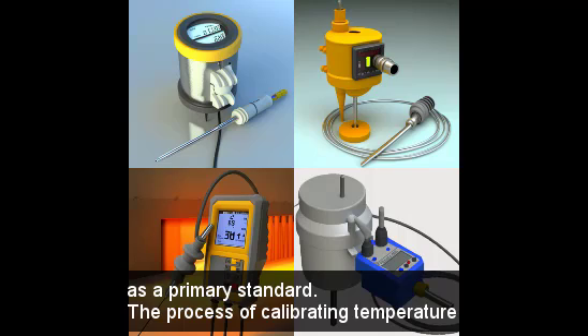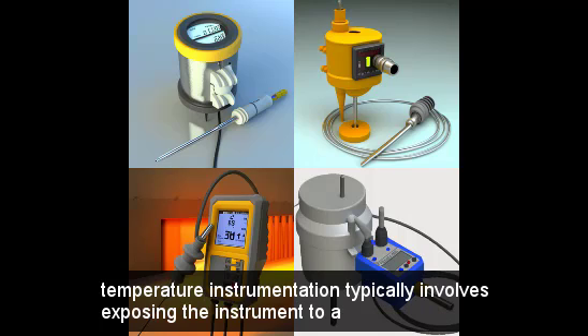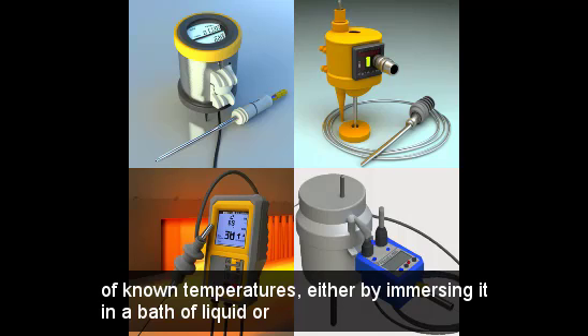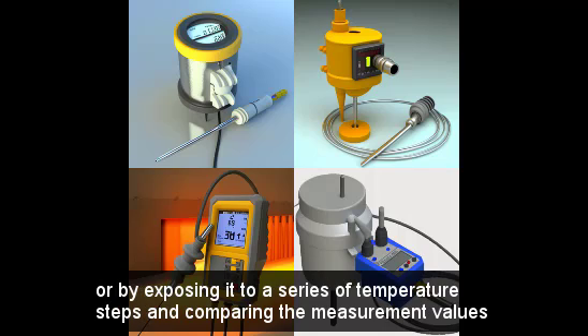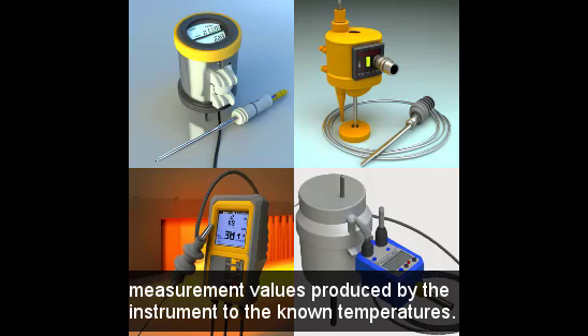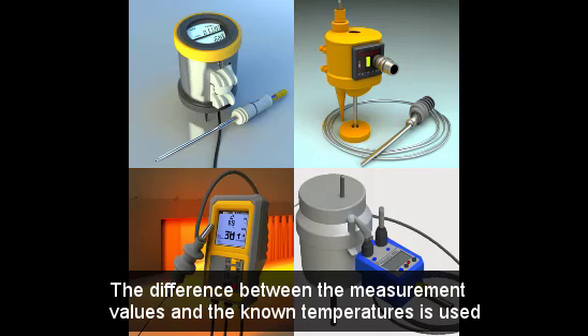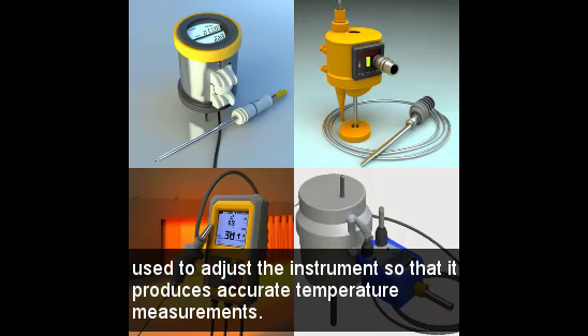The process of calibrating temperature instrumentation typically involves exposing the instrument to a series of known temperatures, either by immersing it in a bath of liquid or by exposing it to a series of temperature steps, and comparing the measurement values produced by the instrument to the known temperatures.